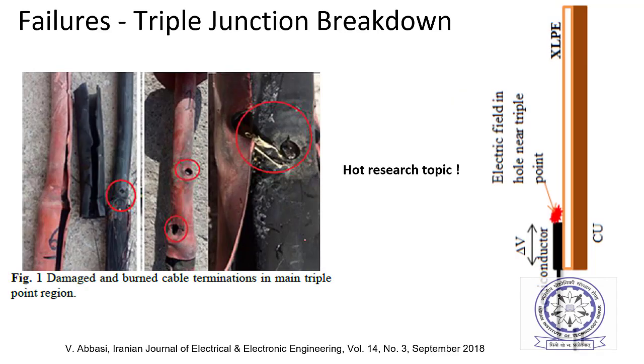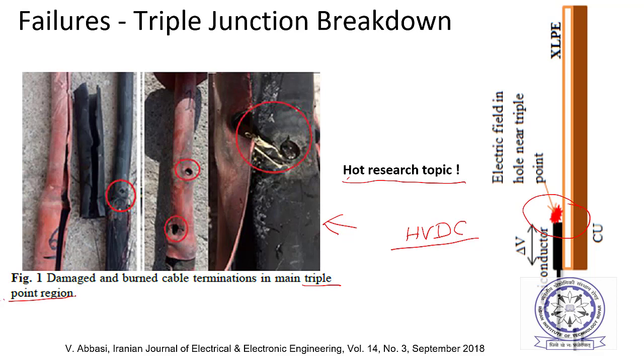Some case reports of failures occurring at the triple junction are shown — this is an active research topic. At the exact junction of three materials — semiconductor, XLPE insulation, and the cable — breakdown occurs. HVDC terminations are not perfect until now and research needs to be done. Even for AC, many failures occur at this triple junction point region.